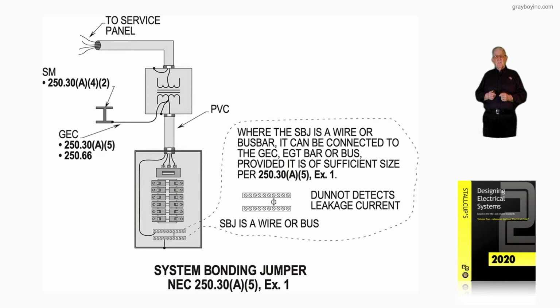Now, this illustration deals with the system bonding jumper. However, we're using it in accordance with 250.30(A)(5), exception 1. Now, notice in the illustration we have two bars there. One bar, the grounded conductor from the separately derived system, is connecting to the isolation bar.